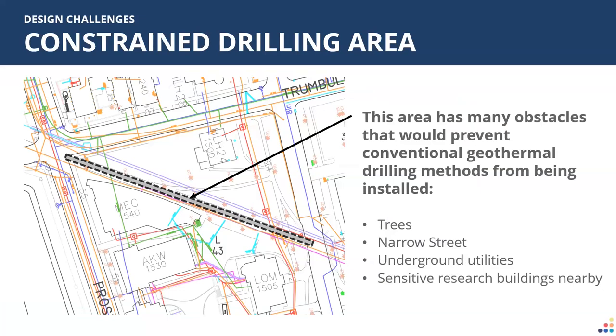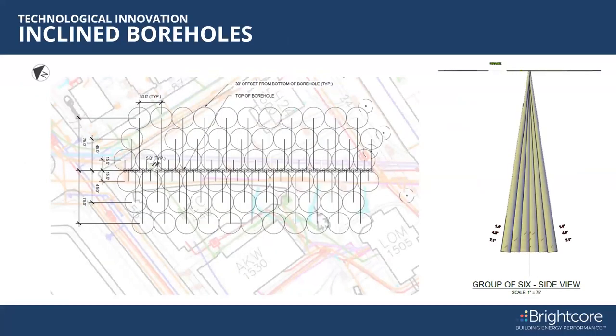And from a specific path, various angled boreholes can be done to then, from a bike path, create over a football field and a half of thermal mass. That's important because tonnage is dependent directly on the amount of exposure time to the bedrock or to your reservoir rock. What that means is that even though measured depth at an angle is longer than your true vertical depth, you're actually maximizing load and tonnage. Think of the vertical position as your least distance, and an angled bore will provide more bang for your bore, as it were. What that does is it minimizes surface disturbance.